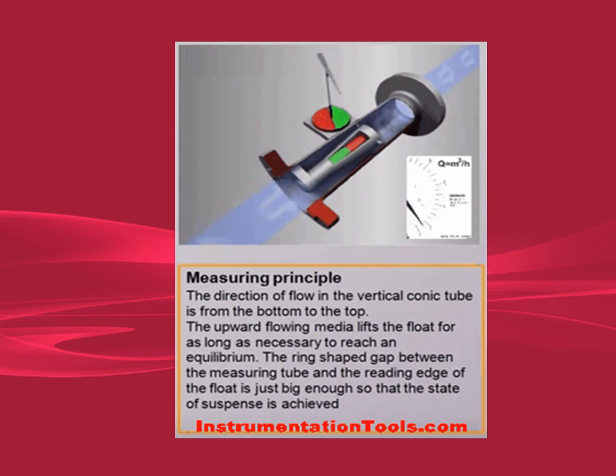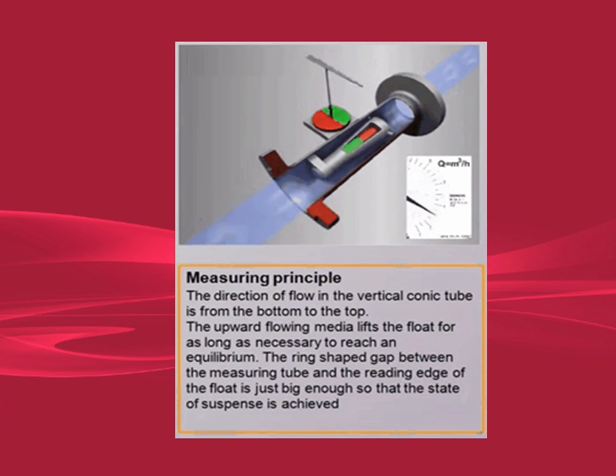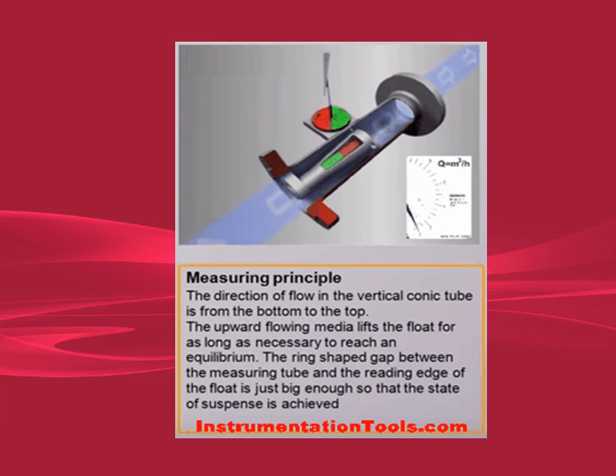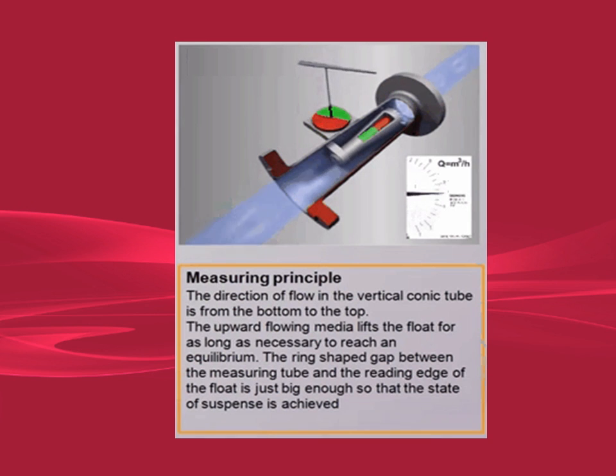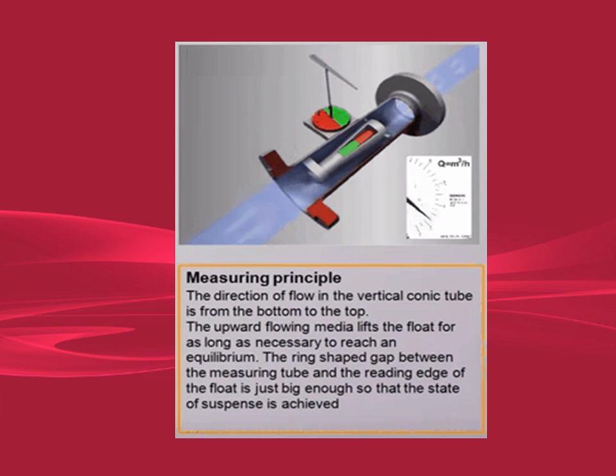A rotameter consists of a tapered tube, typically made of glass, with a float made either of anodized aluminum or a ceramic inside, that is pushed up by the drag force of the flow and pulled down by gravity.